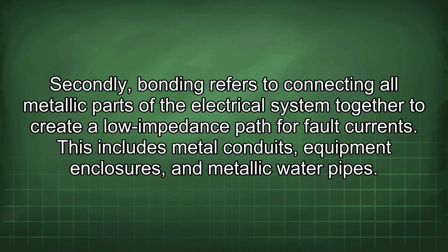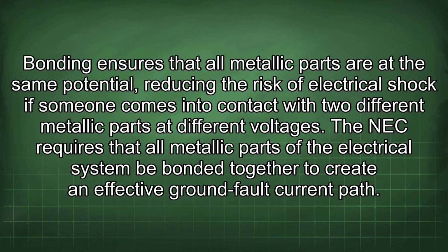Secondly, bonding refers to connecting all metallic parts of the electrical system together to create a low impedance path for fault currents. This includes metal conduits, equipment enclosures, and metallic water pipes. Bonding ensures that all metallic parts are at the same potential, reducing the risk of electrical shock if someone comes into contact with two different metallic parts at different voltages.